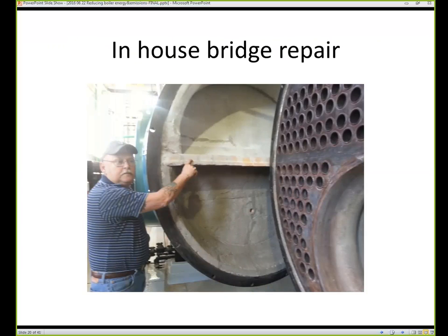This back shelf that you're seeing is an example. We do as much refractory work in-house as we can. On this particular one, we chiseled all that out. We put in the bridge, and then we use different sets of mortar, high temp and low temp mortar. We also graphite the door facings front and back. Every boiler, once a year prior to Class A inspection, we wash down all the tubes thoroughly. In the manway and handhold plates, we also repack all the valves, replace sight glass if needed, and complete any refractory repair. By trying to do everything 98% in-house, it saves us money on the safety device testing and all of it. That way we can put it back into patient care and other things in the hospital.